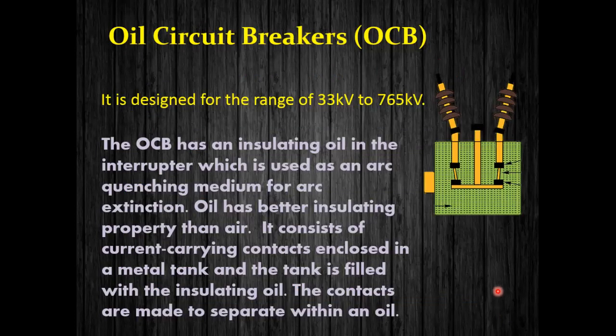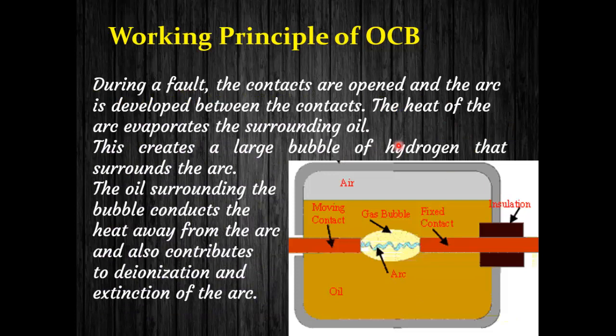The oil circuit breaker (OCB) is designed for 33 kilovolts to 765 kilovolts. The OCB has insulating oil in the interrupter which is used as an arc quenching medium for arc extinction. Oil has better insulating properties than air. The interrupter chamber consists of current-carrying contacts enclosed in a metal tank filled with oil.